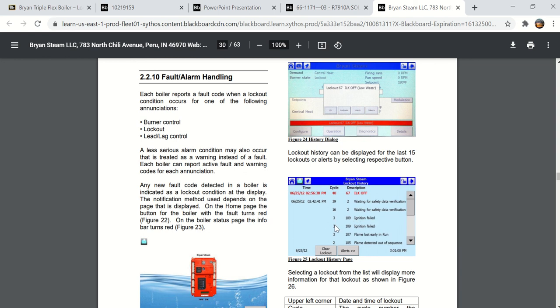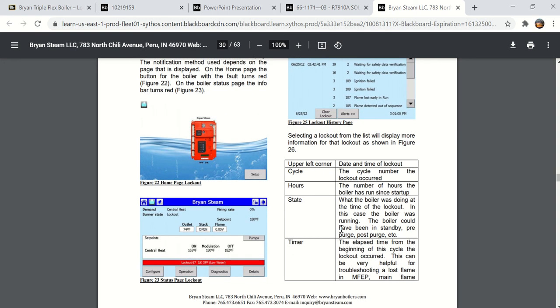It didn't ignite. A cycle only counts if it goes all the way through and the main burner lights. If you see multiple cycle numbers in a row, that just means somebody's hit the reset button. It did not solve the problem. You keep hitting the reset button, you're hoping that something's going to work. If that number doesn't change, you're not being very successful.